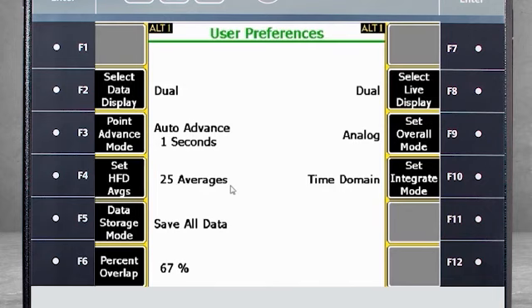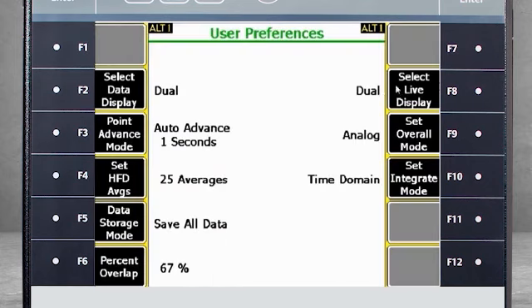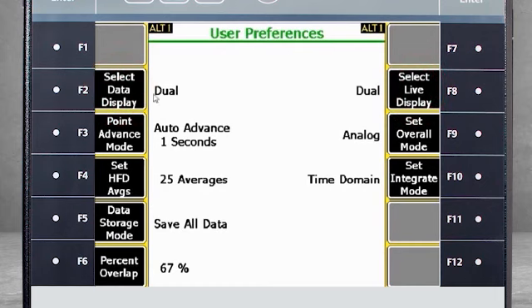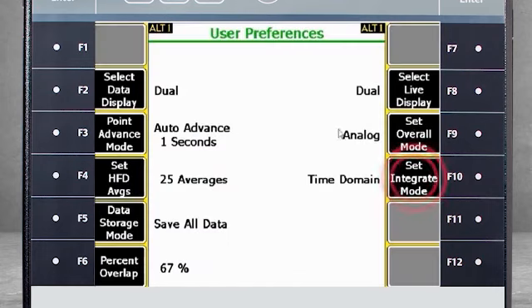F8 Select Live Display is where you can select the data you want to see during collection — toggle between status, spectrum, waveform, or dual. So what is the difference between F2 and F8? F2 defines the data you will see after collection, while F8 defines what you will see during collection. F9 allows you to choose between analog, digital, true peak, and average peak for overall measurements — refer to technical documentation to determine which mode is right for your application. F10 Set Integration Mode toggles between Time Domain and Frequency Domain.